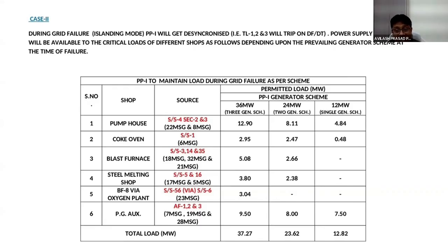If we are running on a single generator scheme, that is 12 megawatt, then we will give power of 4.84 megawatt to pump house, 0.48 megawatt to coke oven. We will cut the power supply to blast furnace, steel melting shop, and oxygen plant, and we will give 7.50 megawatt to our auxiliary units.